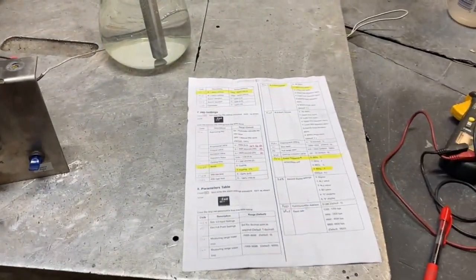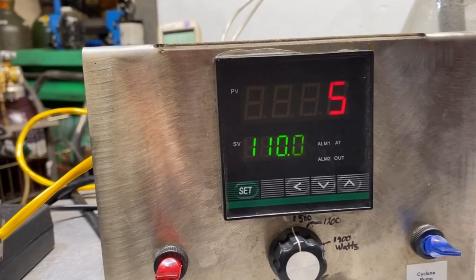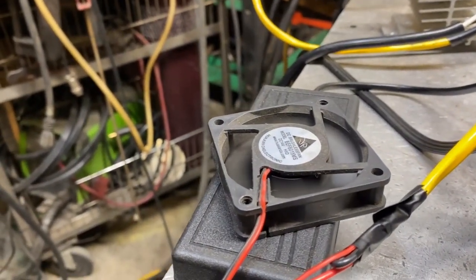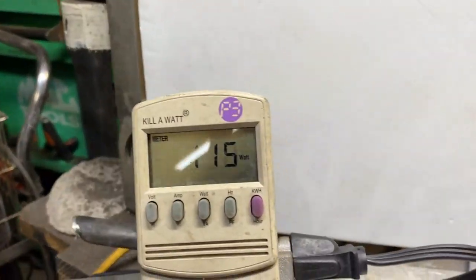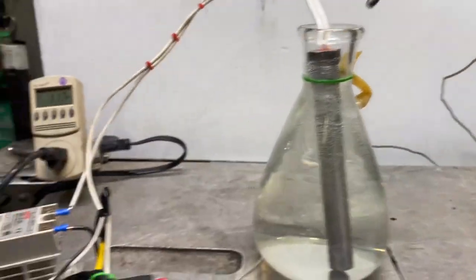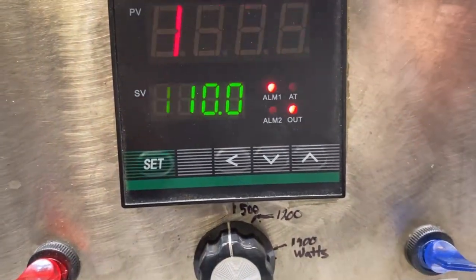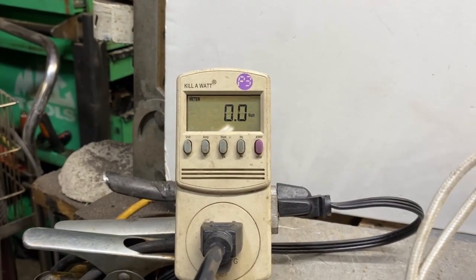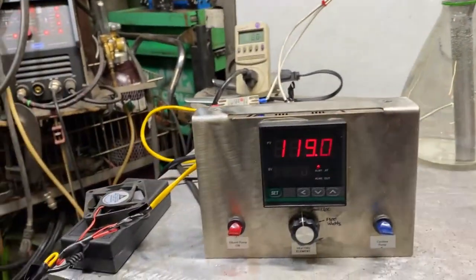And that should pretty much fill you in on the alarm and the different modes. So because your autoclave is now cooling off, the pressure washer boiler pump is on and your gas boiler solenoid is on. So we're going to replace the thermocouple back into the heat and the temperature will rise rapidly. The pressure washer has shut off and the solenoid to the gas system on the burner has shut down.